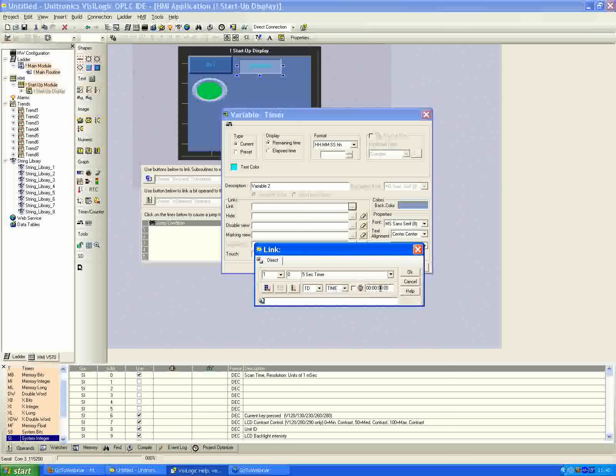If I click the dropdown to seconds format, I can only enter the value in seconds — for example, 120 seconds, which when switched back to time shows two minutes. I don't want that though, so I'll put it back to five seconds for demonstration purposes. The power-up condition here — reset on power-up — means whenever you cycle power to the controller, it automatically loads this predefined time into the timer.